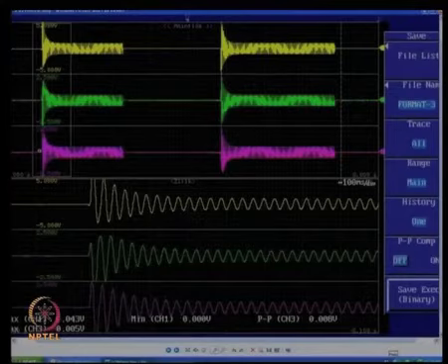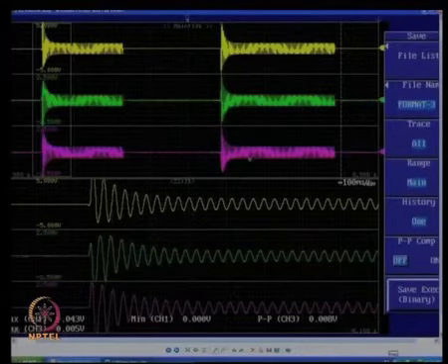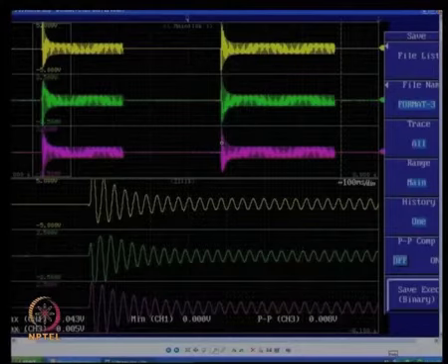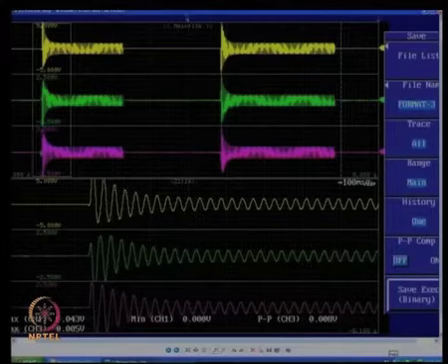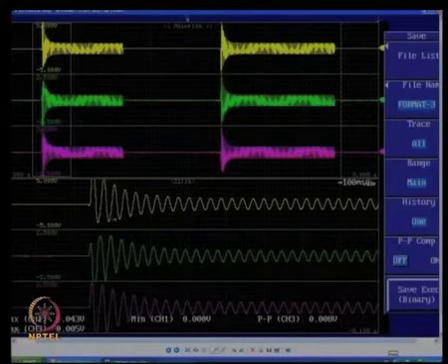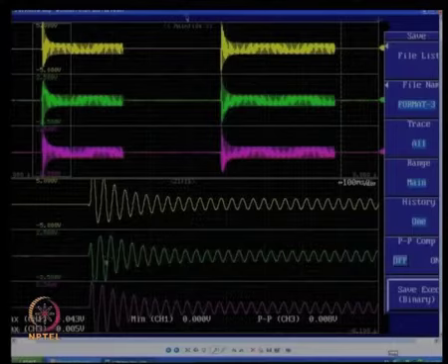You will notice that when you applied the short circuit the first time and the second time the waveforms look a bit different. That is because the DC component when we applied the short circuit is different from the DC offset component. It really depends on the instant of short circuit, what point on the sinusoidal waveform did you apply the short circuit. You actually see different DC offsets in the different phases, but one thing is clear: there is a DC offset which you see very clearly here, and also the overall envelope of this waveform decays with time.